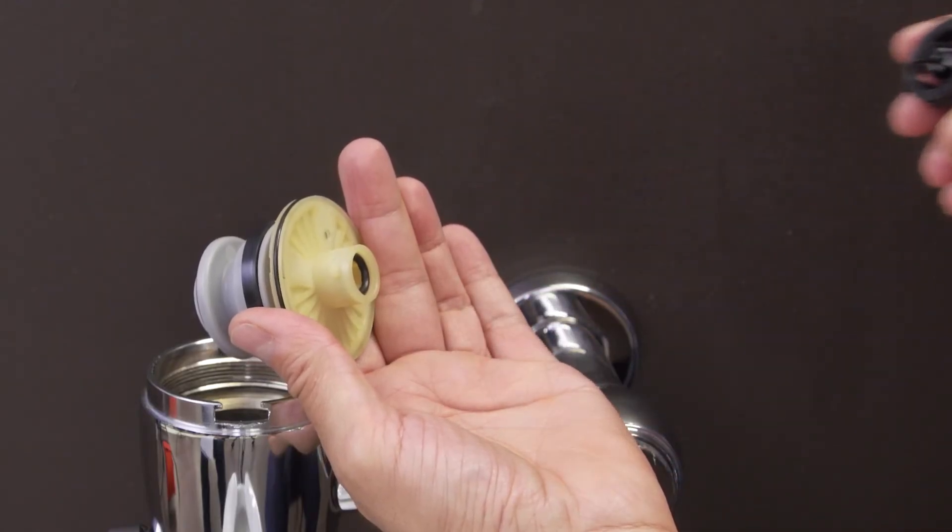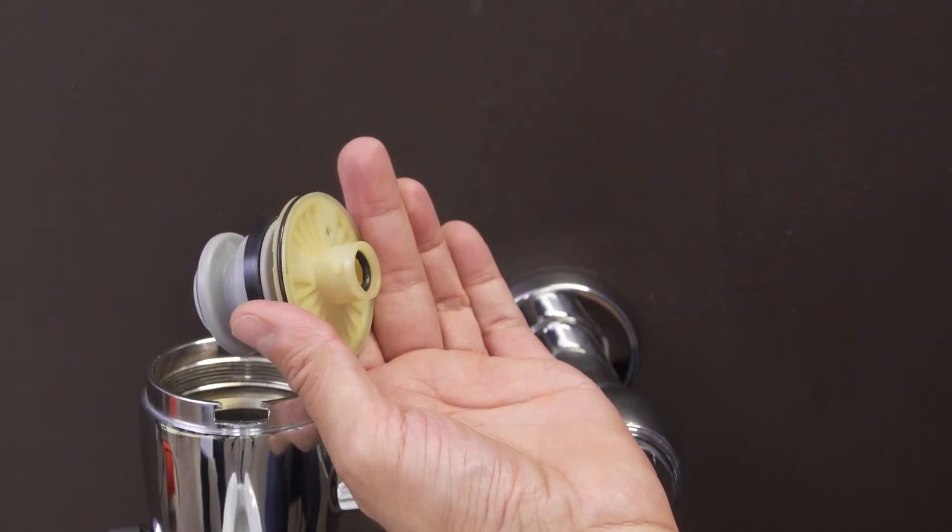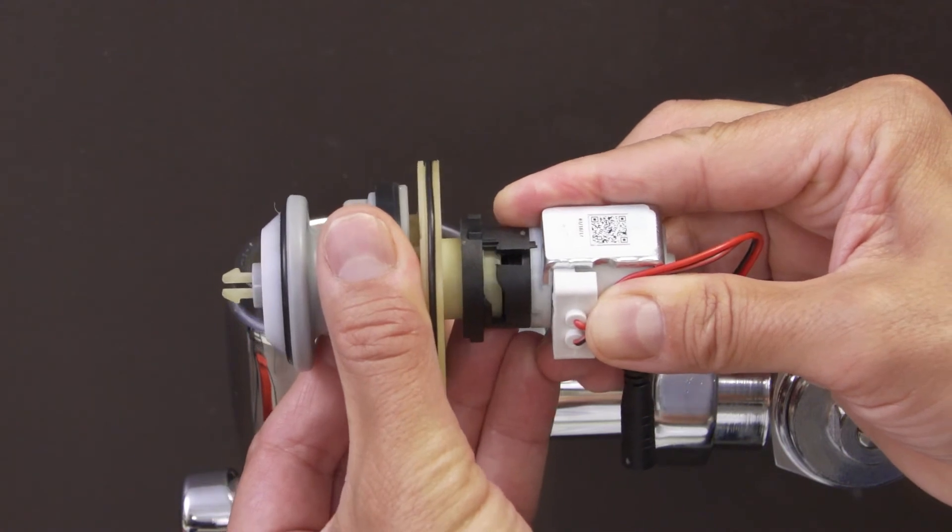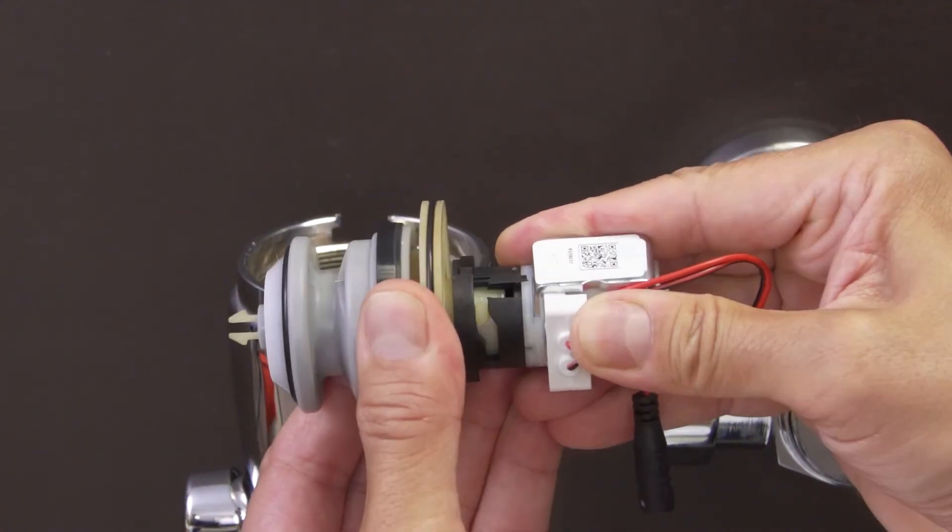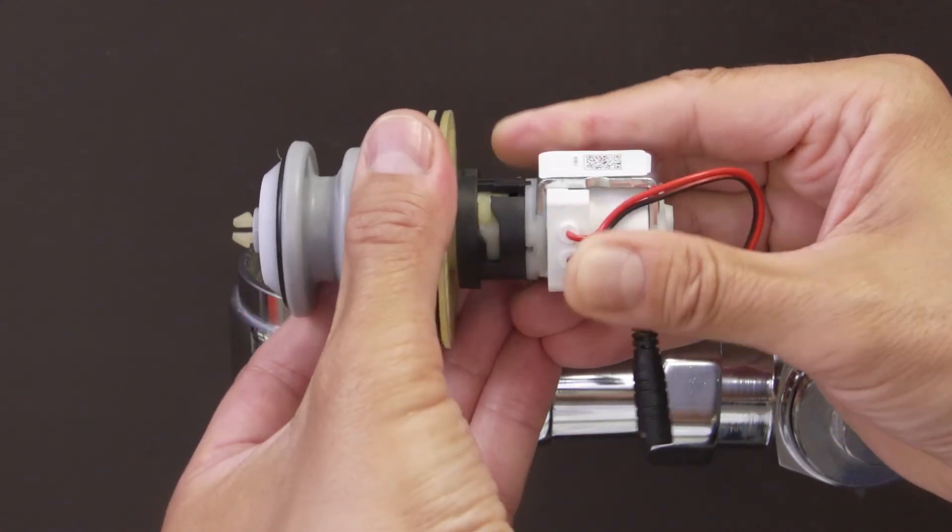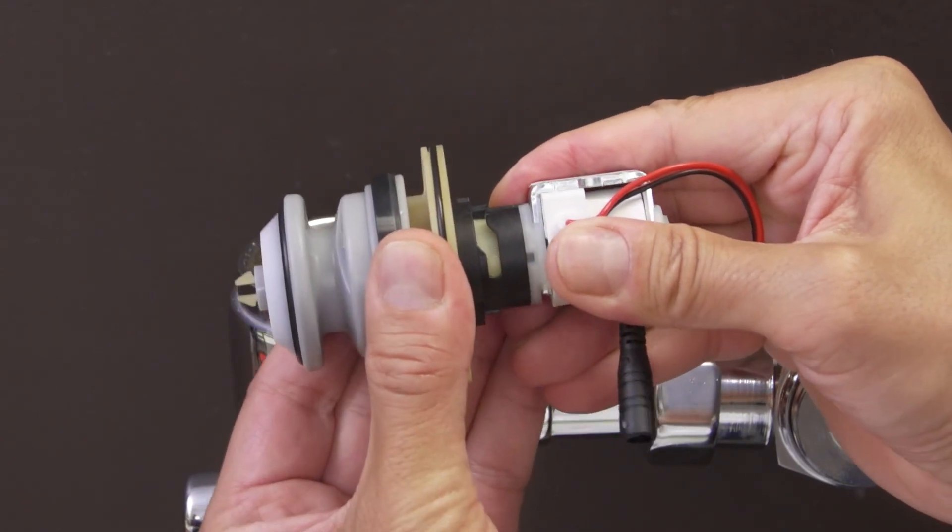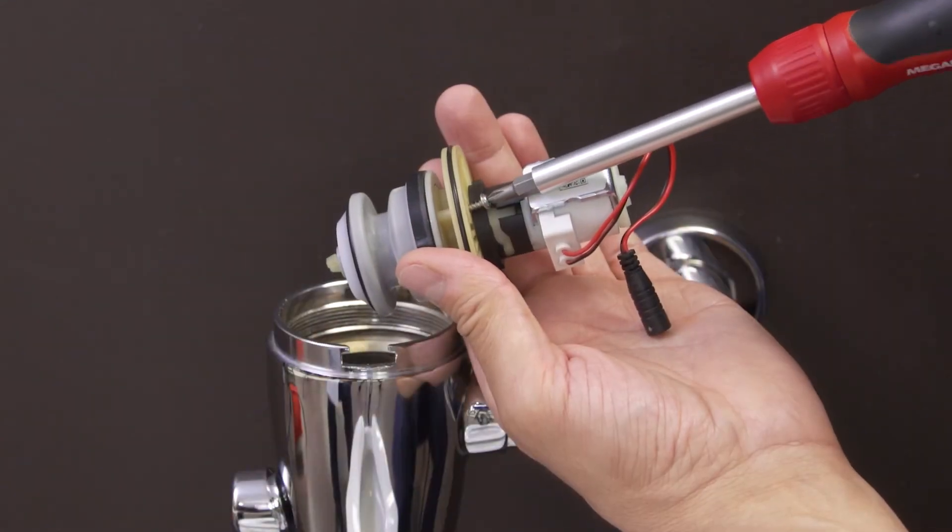Next, discard the old solenoid. Push the new solenoid into the piston. Rotate it a quarter turn clockwise to lock it into place. Now tighten the locking screw.